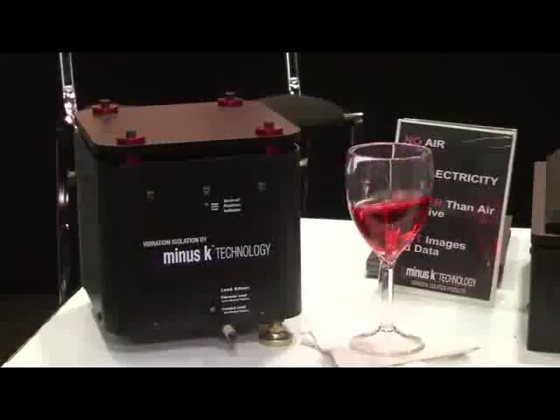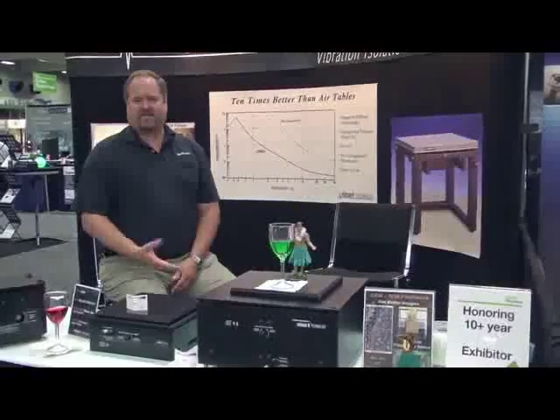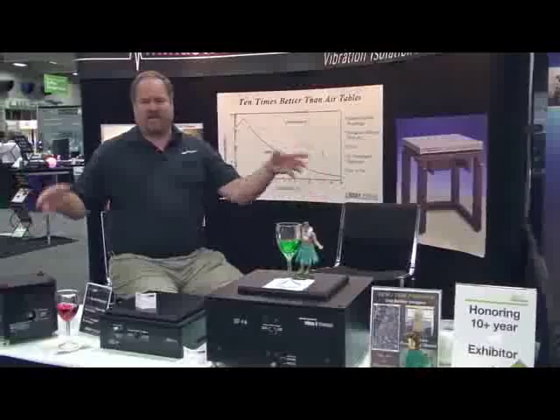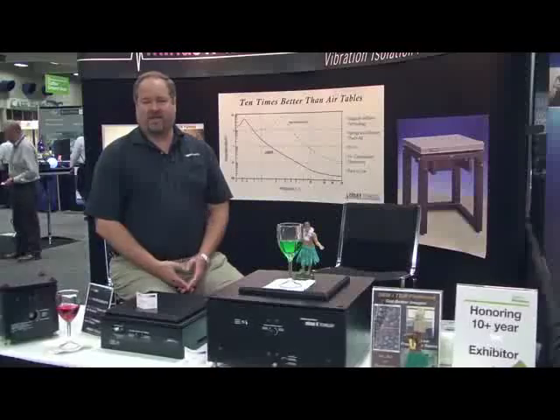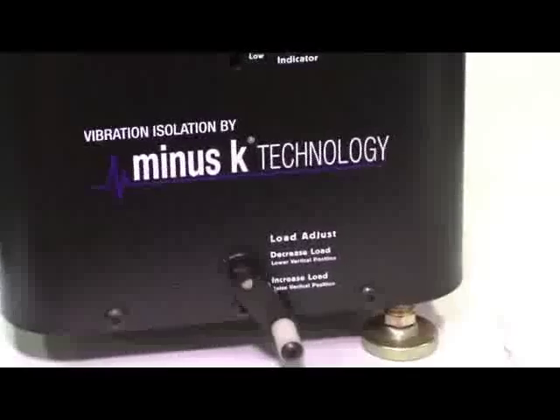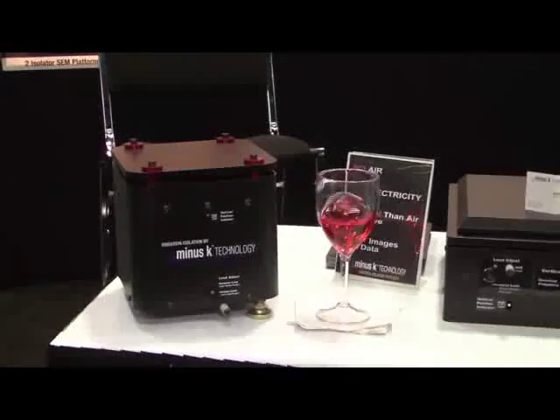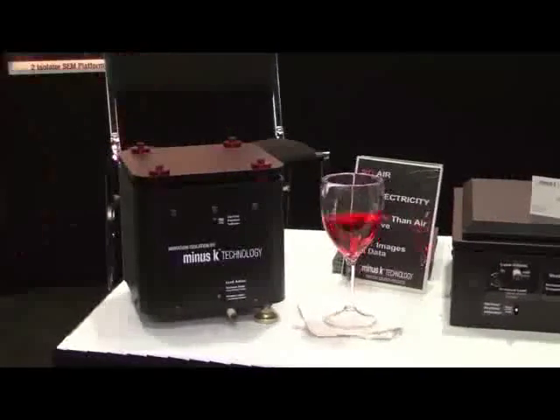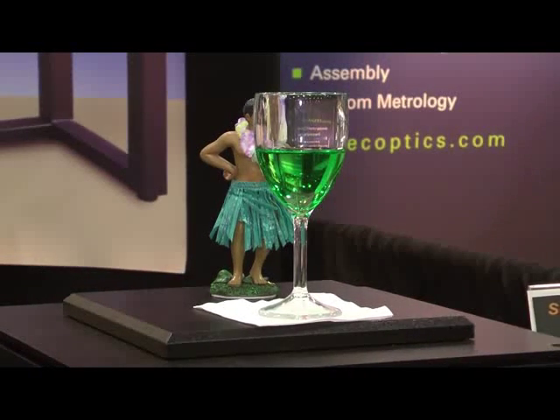There are other passive isolators on the market. Ours are a little different. When people think of passive isolators, they typically think of air tables — the big air tables that have the air bladders, big optical honeycomb breadboards and so forth, that have been around for many decades. Our isolators are also passive, but they couldn't be more different. Our isolators use no air, no electricity. It's all springs and flexures internally. What that means to you is that you can have a benchtop isolator that gives much better performance than a typical air table in a much smaller package that doesn't require any air or any electricity.